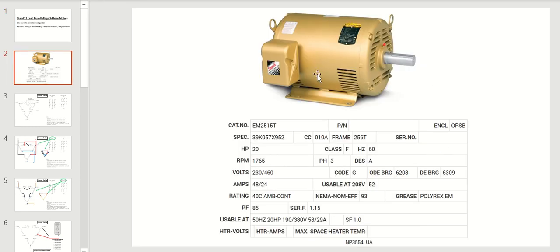Here is a typical Baldor Reliance base mounted motor, very typical for HVAC applications. Here's the nameplate that you'd see on the motor. It tells you a lot of information. It does not necessarily tell you how the motor is connected internally and does not really give you the information you need to test the resistance of the windings.